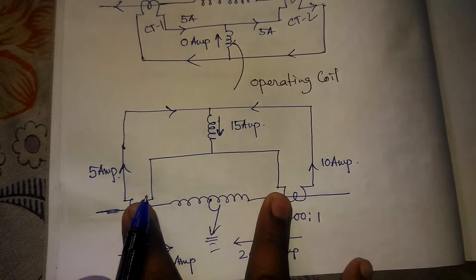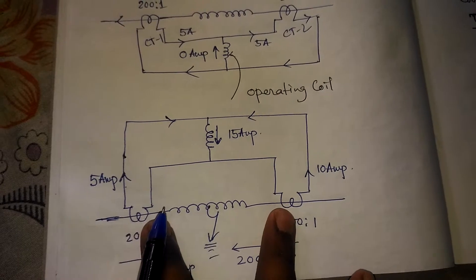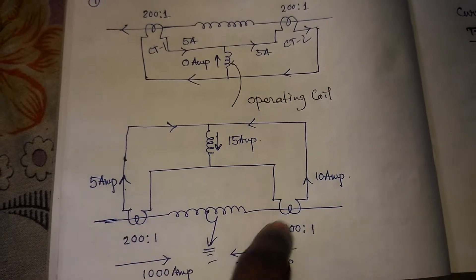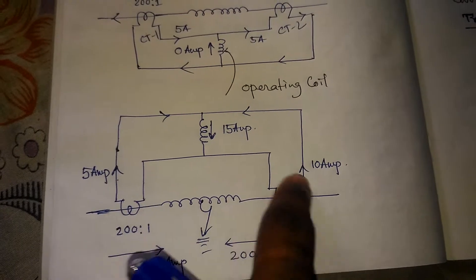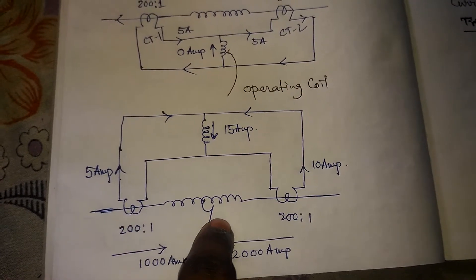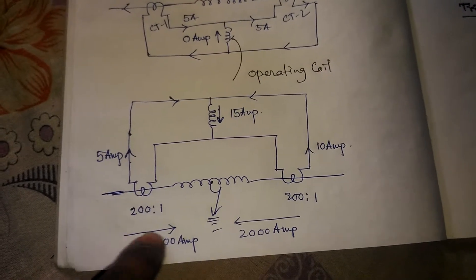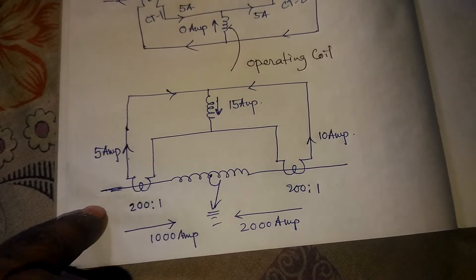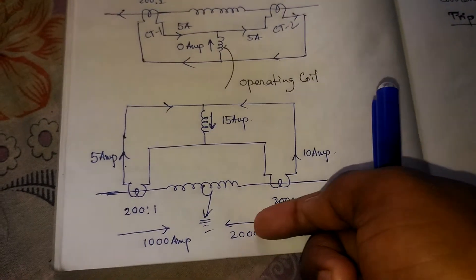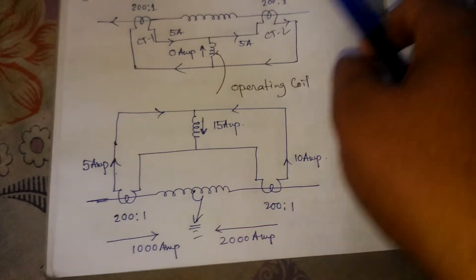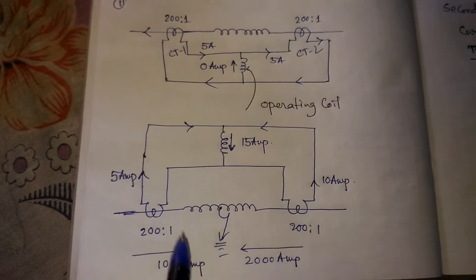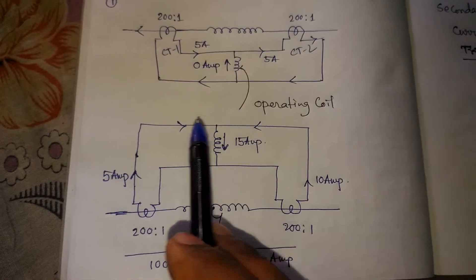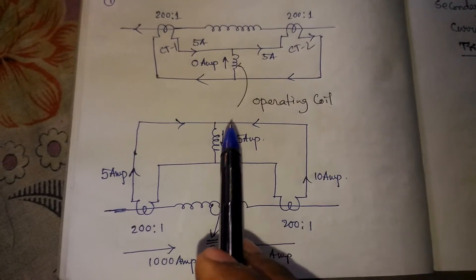If some internal fault occurs in between these two CTs — this is also called the restricted zone, or restricted zone protection — the current flows to the point of the fault. Suppose 1000 amperes fault current is flowing in one direction and 2000 amperes fault current is flowing from the other direction. The secondary current from CT1 will be 5 amperes and from CT2 will be 10 amperes. So the two currents are added: 15 amperes is flowing to the relay coil.